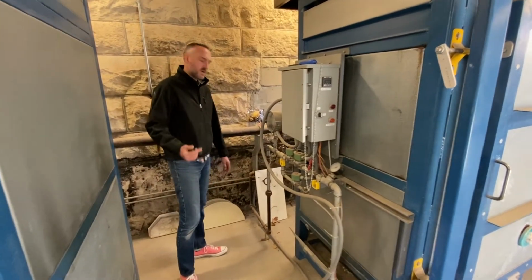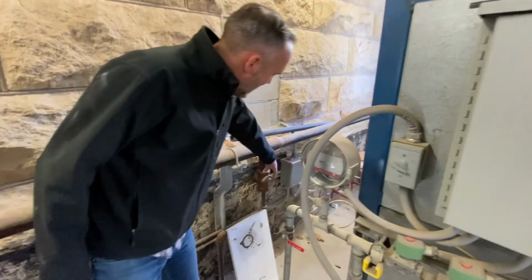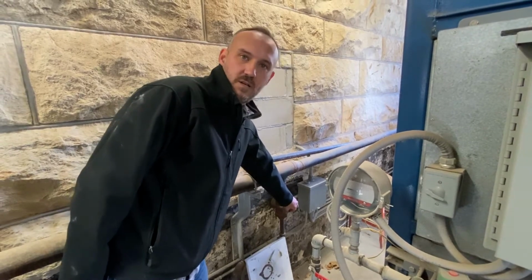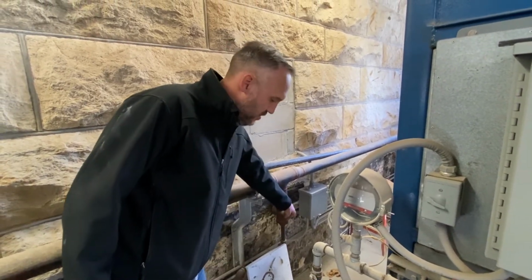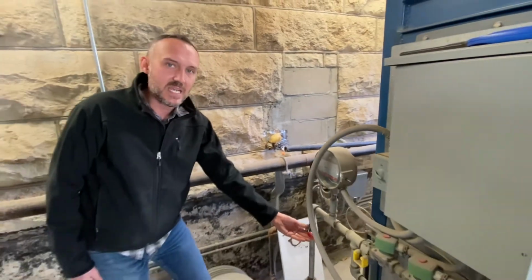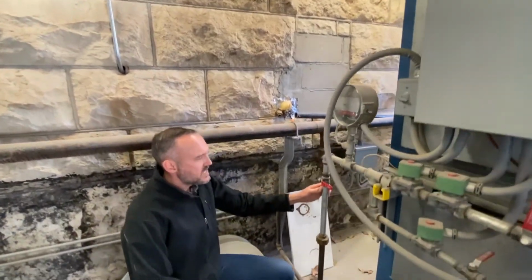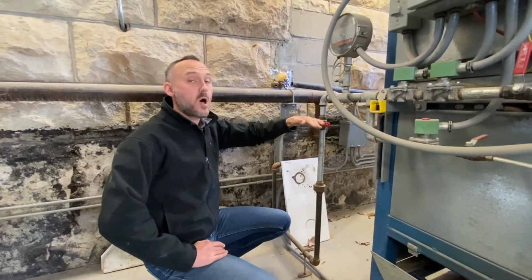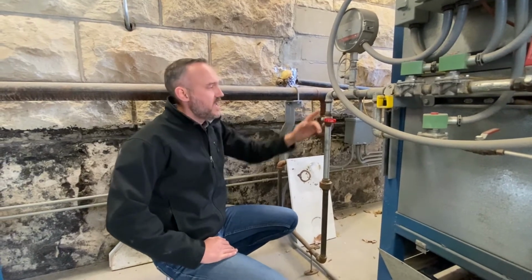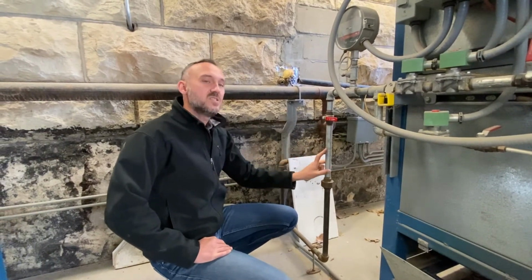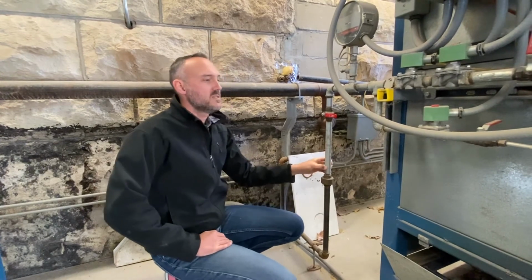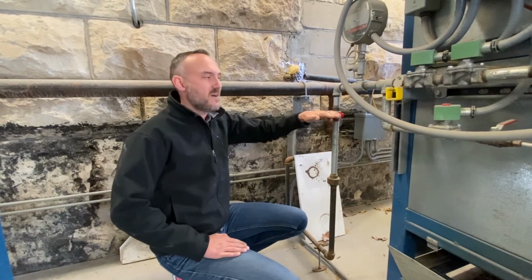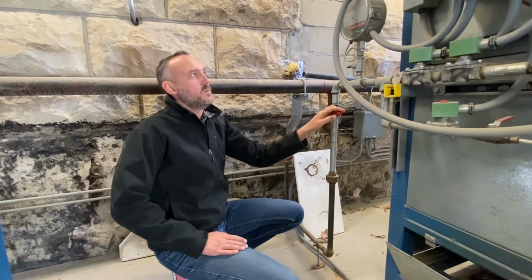And if you'll follow me, camera, this would be our master on for a given kiln. This should never be turned off, essentially, unless it's done by an instructor or grad student. Our first on-off valve is right here. And one other thing about gas kiln valves and valves in general: when the handle is perpendicular, in almost all cases, this means that it's been turned off. If it's parallel with the pipe, that means on. I have seen some circumstances overseas where that's not the case, but the vast majority of them, perpendicular is off, parallel is on.